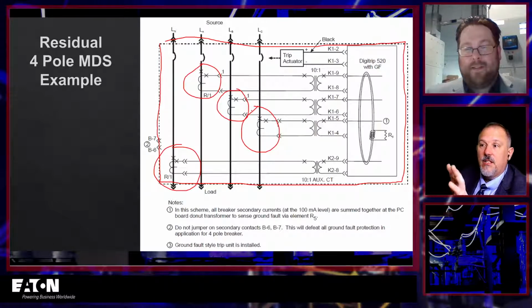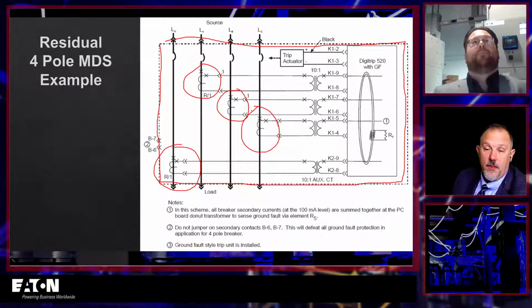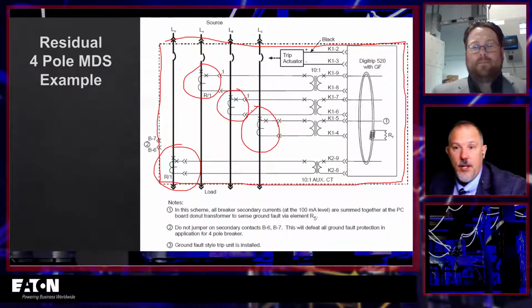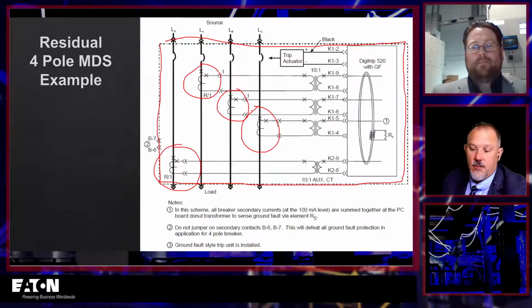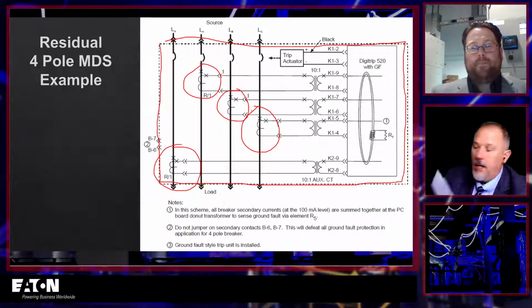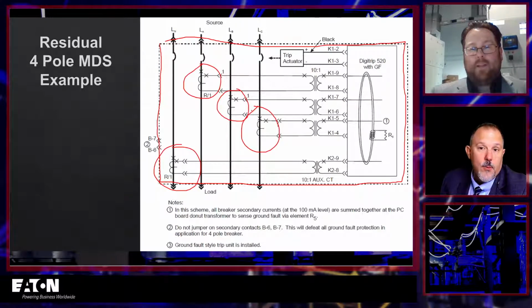You would be testing its full functionality, doing primary current injection testing, tests everything, right? And that would be my argument that it's not for nothing, because I've heard people say, well, you're just making me test this thing. It was tested at the factory. I got a test report right here, and it says it was working when it left the factory 6 months ago, and now I'm installing it, and you're telling me I got to test it again. But you don't know whatever happened to that breaker in those 6 months. So, I mean, it's just a level of insurance.